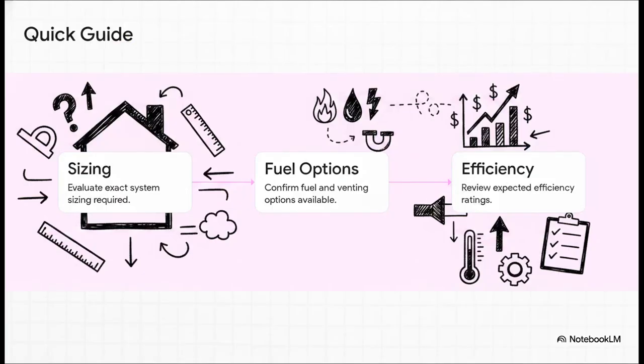So what exactly do you do next? When you're ready to make the call, take these 3 actionable steps. Step 1: have an installer perform a strict manual J load calculation. Guesstimating size based just on square footage is a guaranteed way to ruin your efficiency. Step 2: confirm what fuel sources and venting options are actually available on your specific property. Step 3: sit down and rigorously review the expected efficiency ratings and installation details with your HVAC professional so there are 0 surprises on installation day.